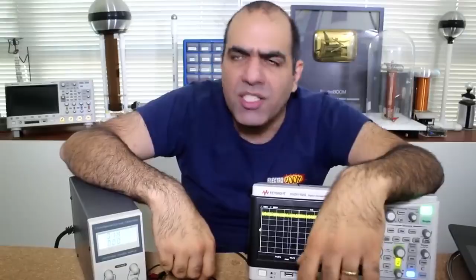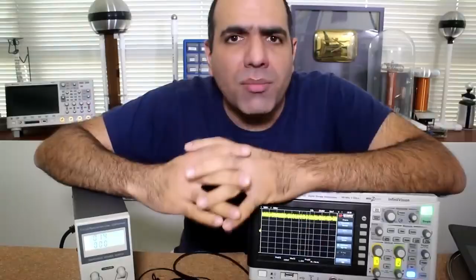That's why in AC power lines, they keep them well above ground and far apart to reduce those stray capacitances. But in some cases where we need to run the power under the salt water of the sea, say between United Kingdom and Europe, or underground in the cities, the line-to-earth capacitance becomes huge, sucking so much AC power because the wire is right beside earth or water. This will waste a lot of active and reactive power where DC doesn't have any problem whatsoever.